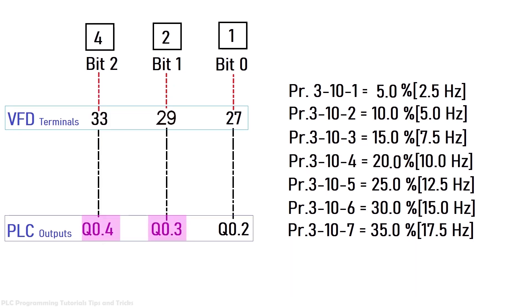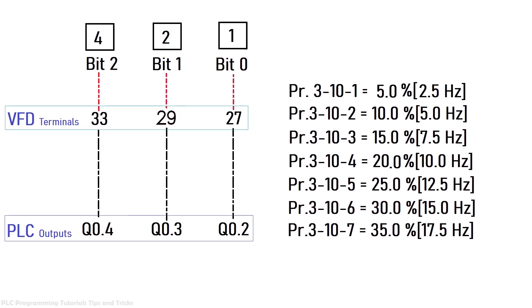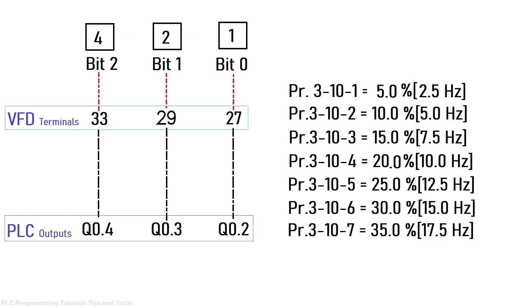If we turn on Q0.4 and Q0.3 together, it activates bit 2 and bit 1. The sum of their values is 6, loading preset frequency reference 6 — 15 Hz — and the motor will run at 15 Hz. If we turn on all three outputs of the PLC it activates all three bits, their sum is 7, loading preset frequency reference 7 — 17.5 Hz. So now we understand how to select different preset frequency references using the PLC digital outputs.